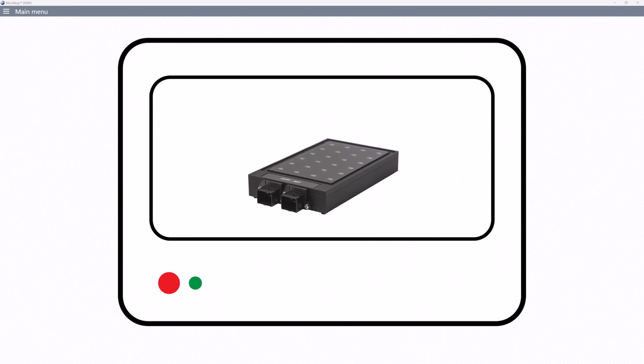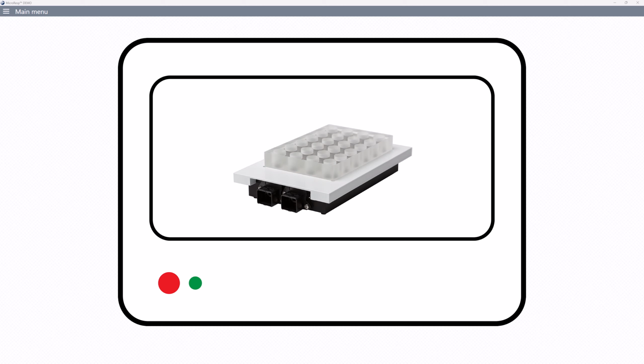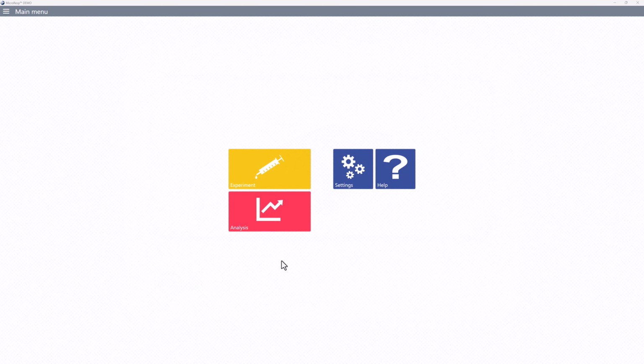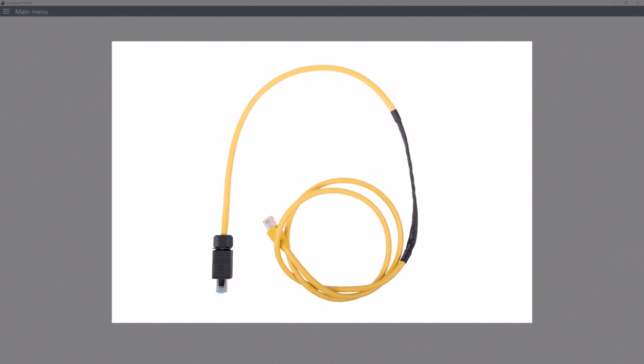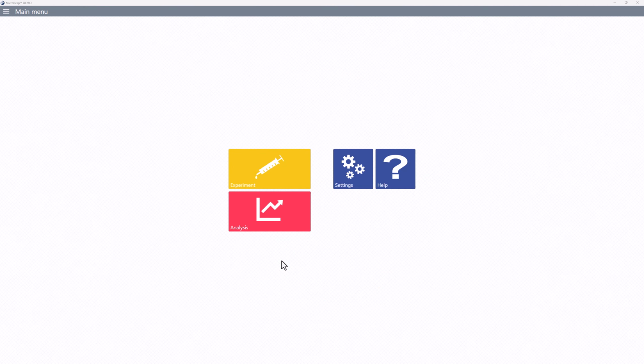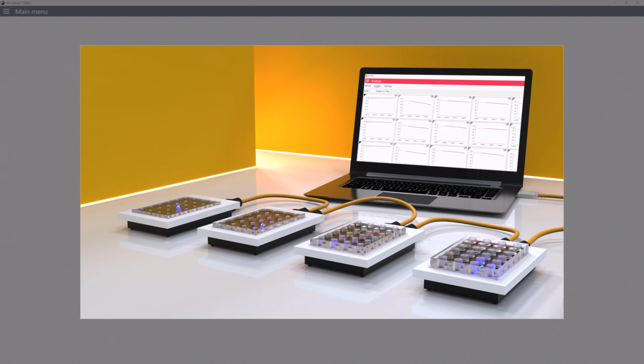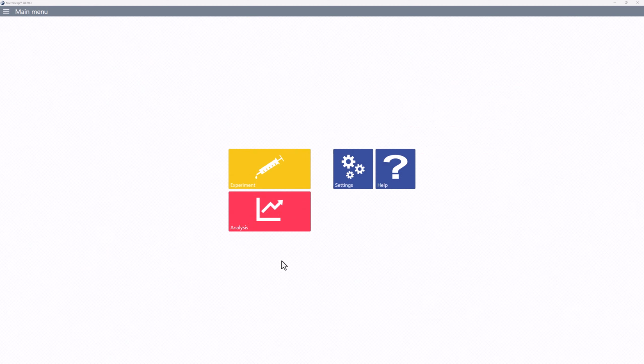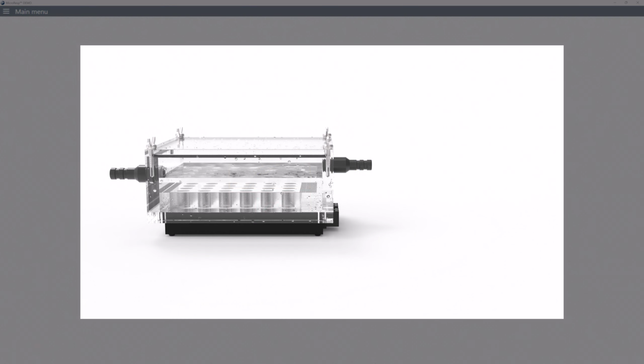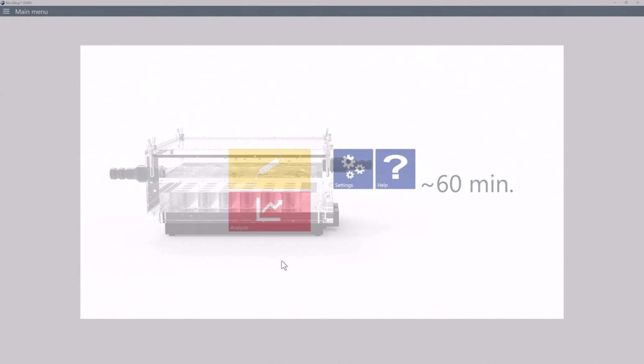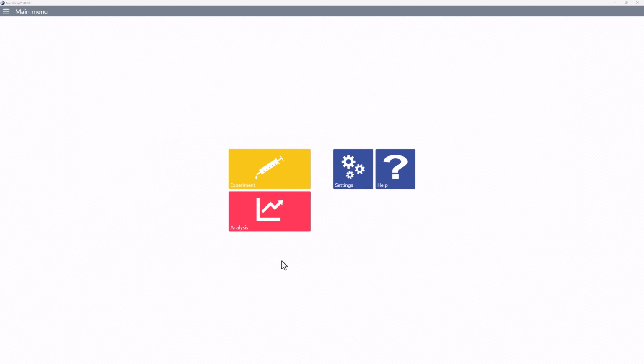If using an incubator, place the included white plastic guide on top of the reader, the glass plate into the guide, and then keep only the reader, guide, and glass plate in the incubator. Note that the long yellow reader cable comes with a flat black part, so that you can keep the incubator door closed. Finally, the entire microplate system can be placed in a climate-controlled room. We recommend leaving the setup at the experimental temperature for around 60 minutes prior to an experiment to obtain a stable temperature before starting measurements.